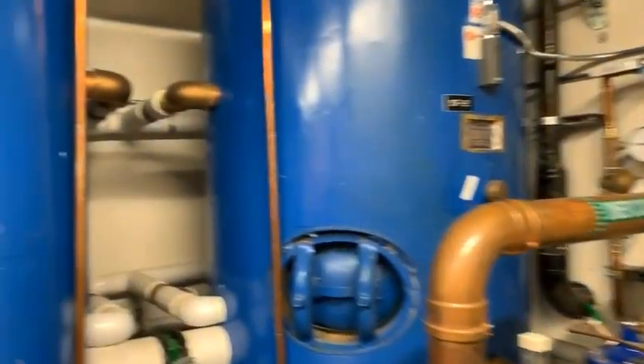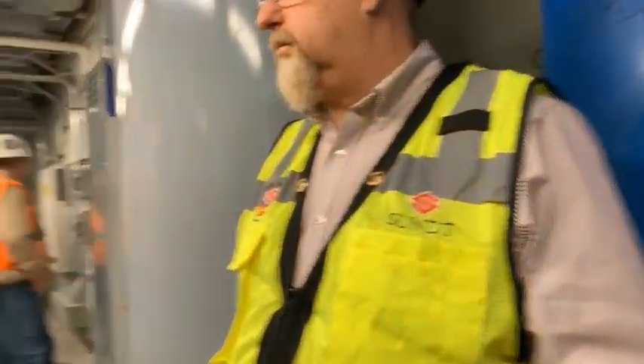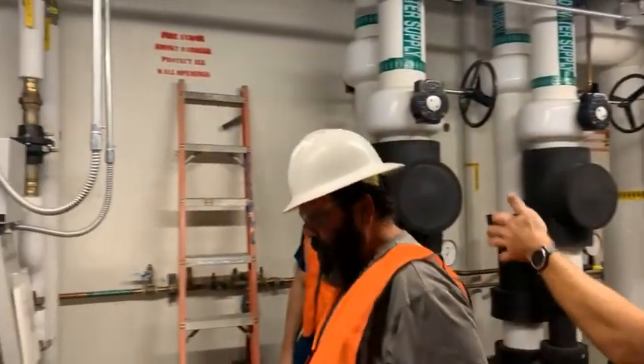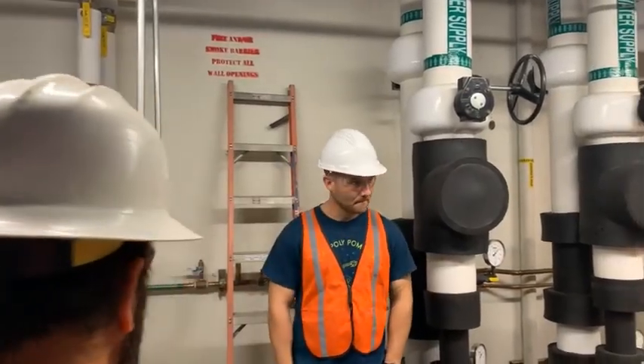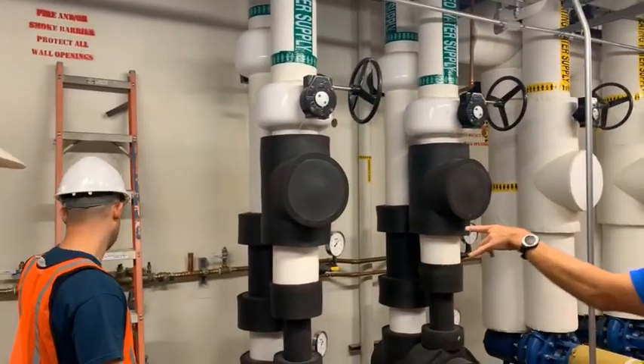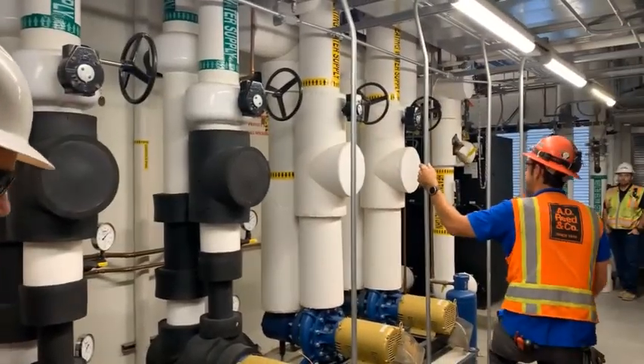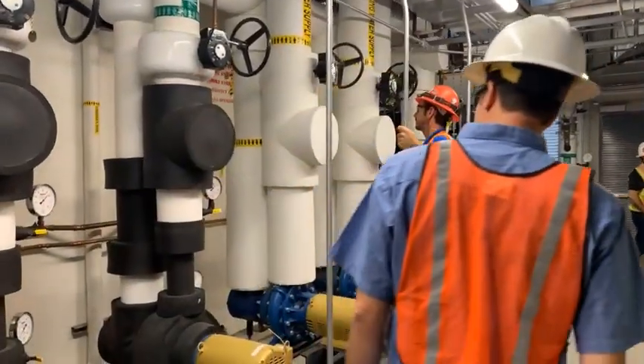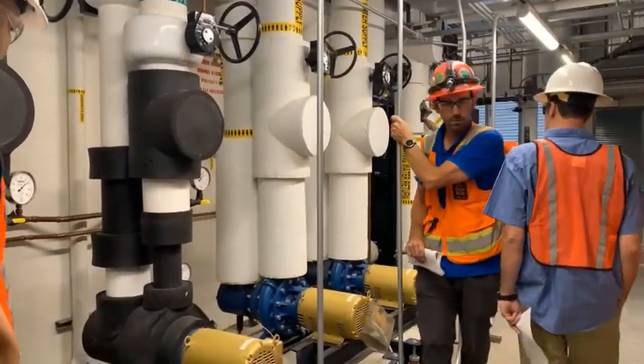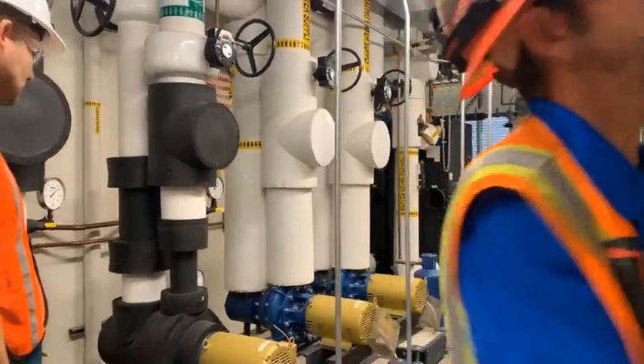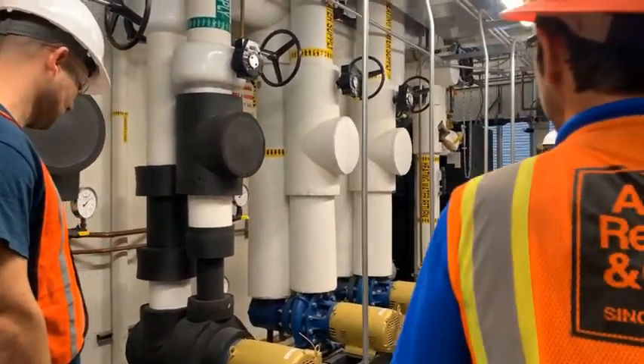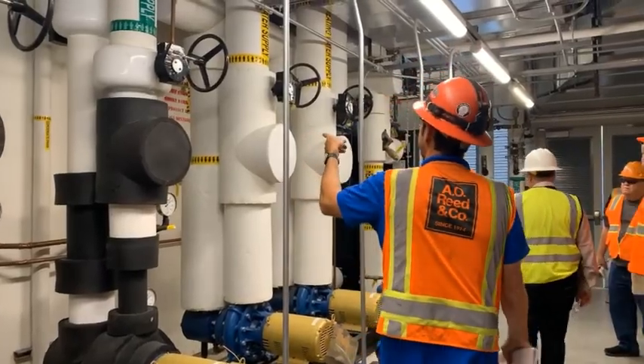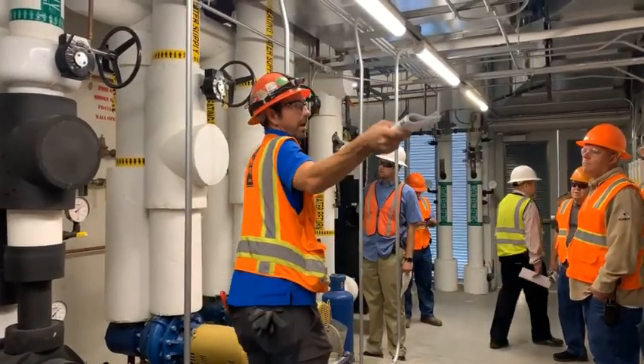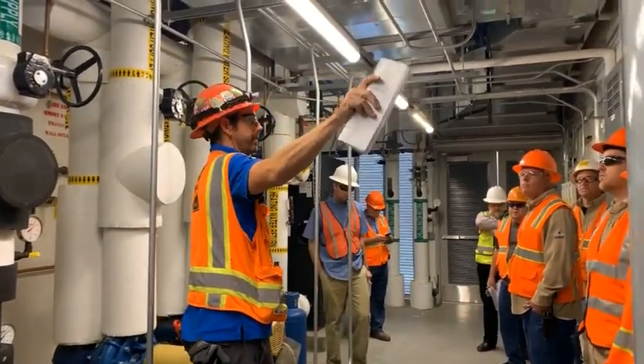Moving back out of this room, we have a water line that comes over. There's a backflow. From the backflow on is going to be your heating hot water makeup. The backflow's here. The pressure reducing valve station's up here. The set point on the pressure reducing valve is 57 pounds. Again, we've checked the charge on the tank is 1 psi below that, 56 pounds.